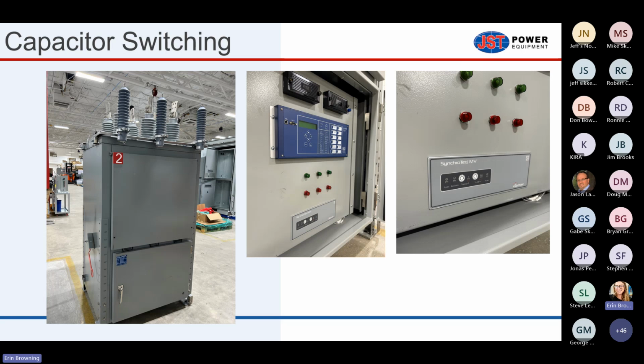There's two different applications that we can talk to customers about. One is cap switching and one is reliability improvements. Capacitor switching, we're talking about closing the breaker on at zero crossing, at 0 volts. And this is to minimize inrush current across the vacuum bottle contacts. We can achieve this using a third-party controller.